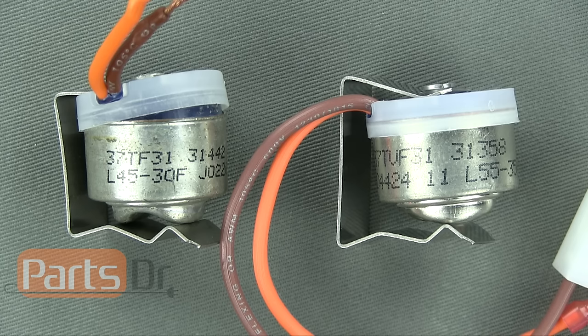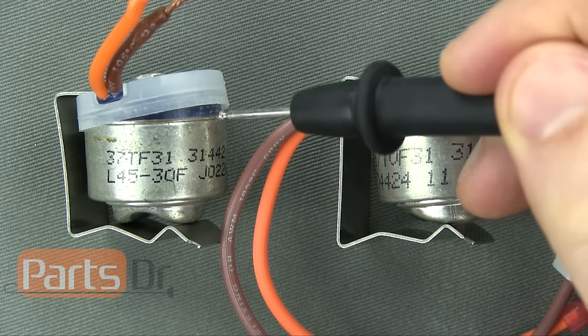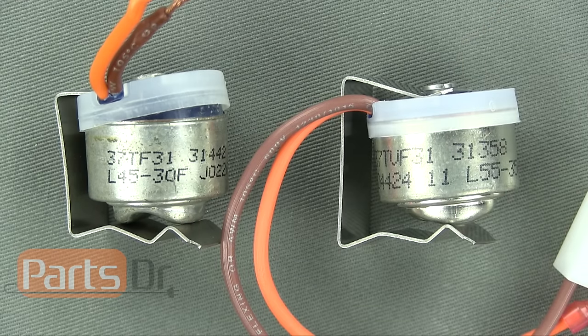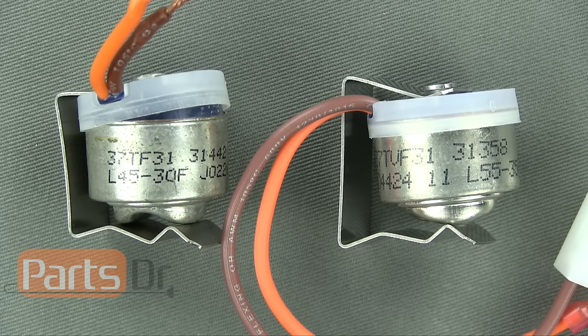The thermostat on the left is a bad defrost thermostat, and you can see how the top is raised up and some of the blue color from the inside is showing. The thermostat on the right is a good thermostat, and the top is not raised up at all.